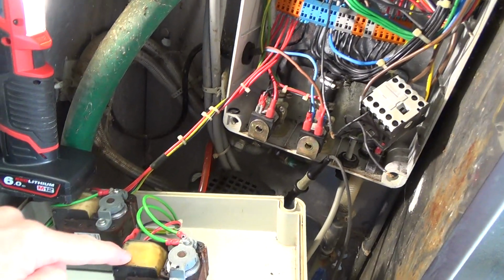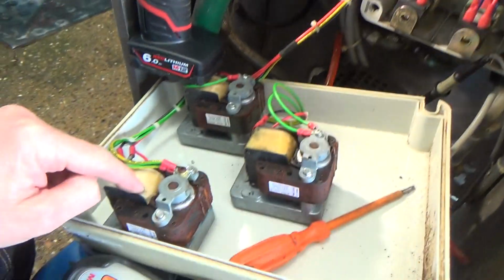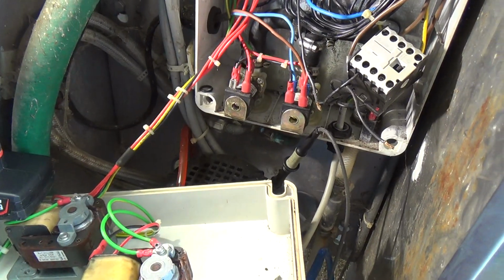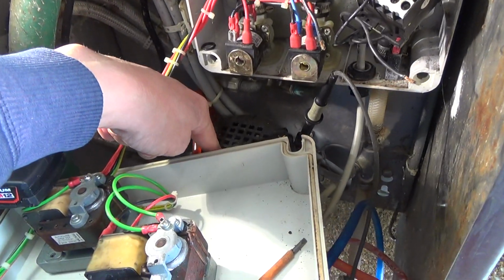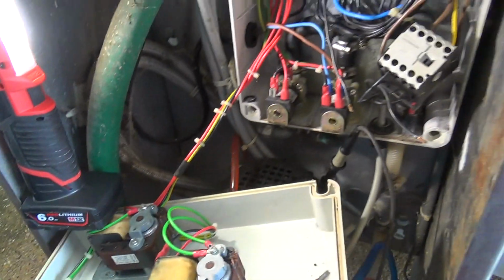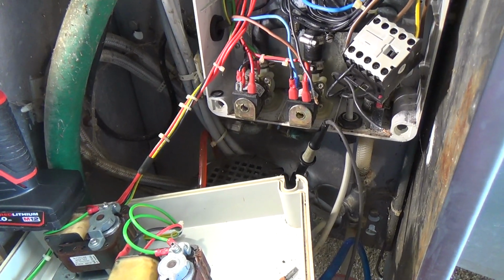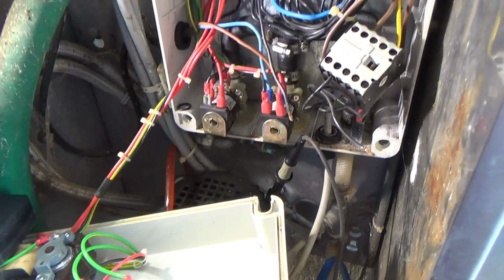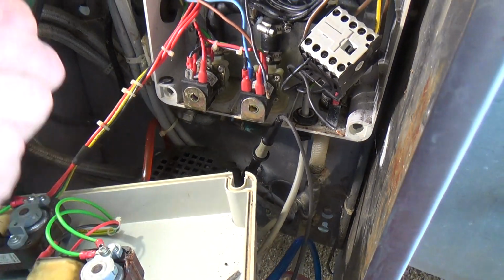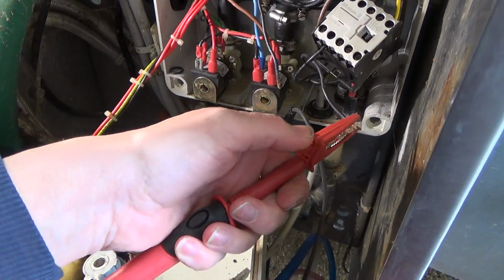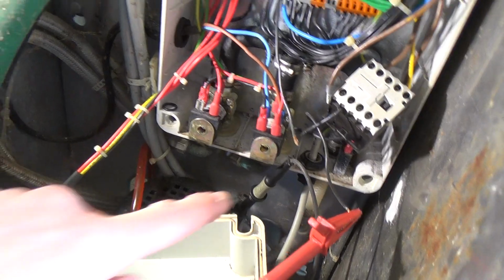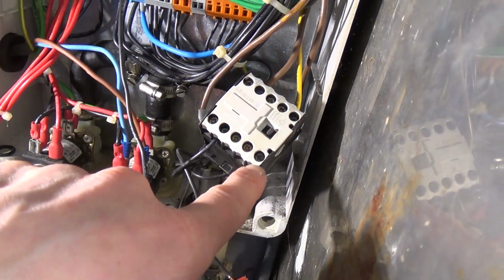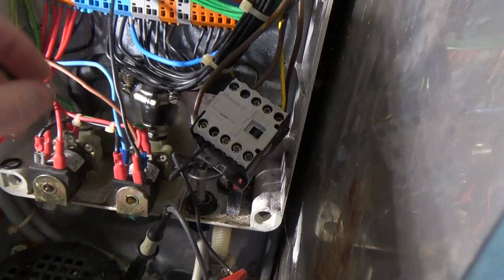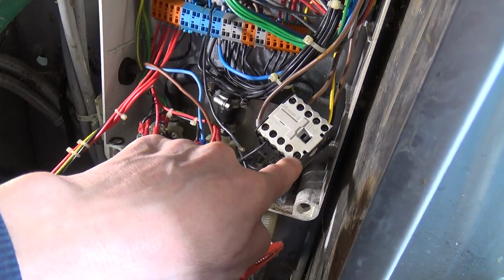Okay, so we've tested the hot valve, the cold valve, the hypo, acid and alkaline pumps. They're all looking good. So the other things we've got is the water pump, drain valve down there, and then there's 2 agitators on the top of the tank. Now the agitators run when it's cooling, so it's odd that the fault would only show up in washing. Anyway, so this is we think is the neutral for the pump. I haven't checked it, I'd have to trace the wires, but that was piggybacked into A2, which is a coil connection for that thing, and then the 2 were dabbed in together, so they were getting a neutral to the pump by using that as a terminal.